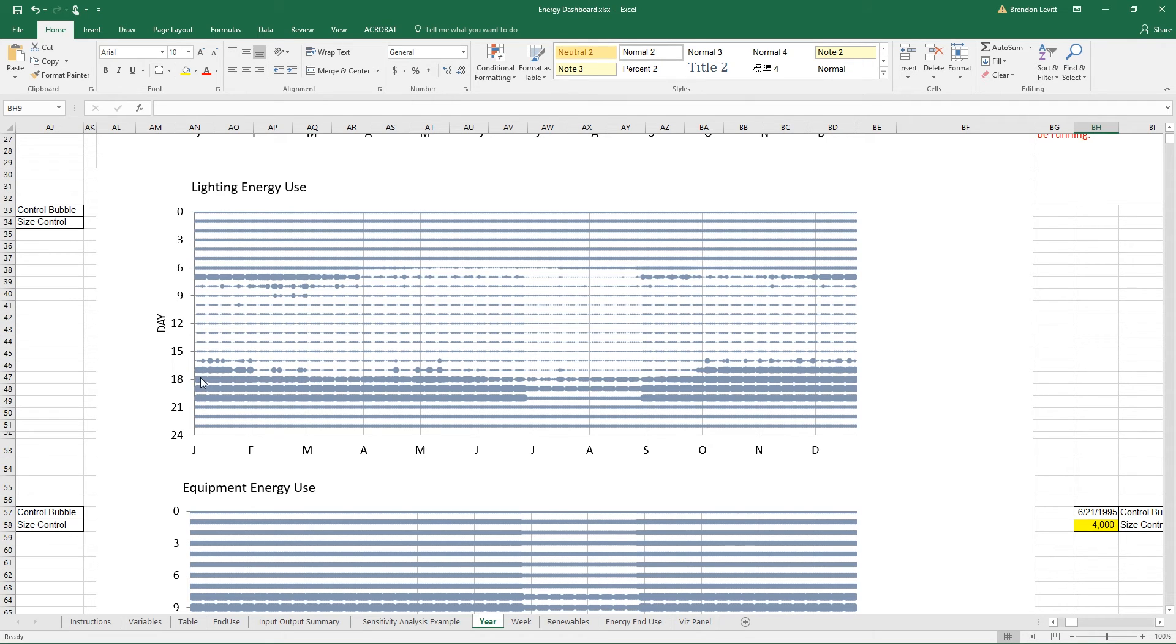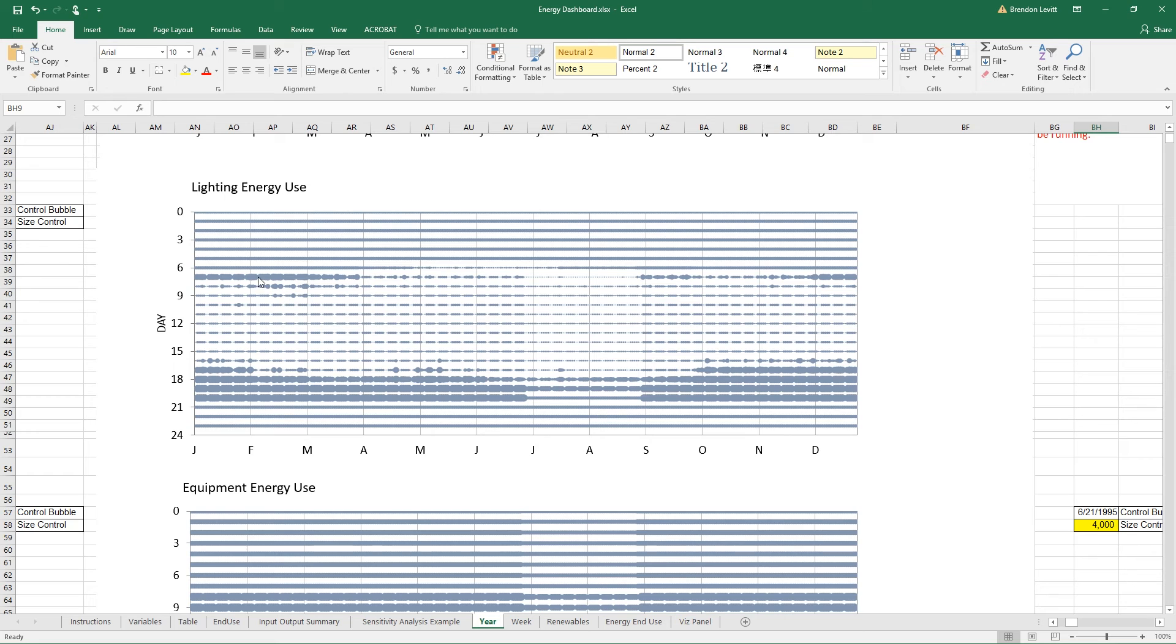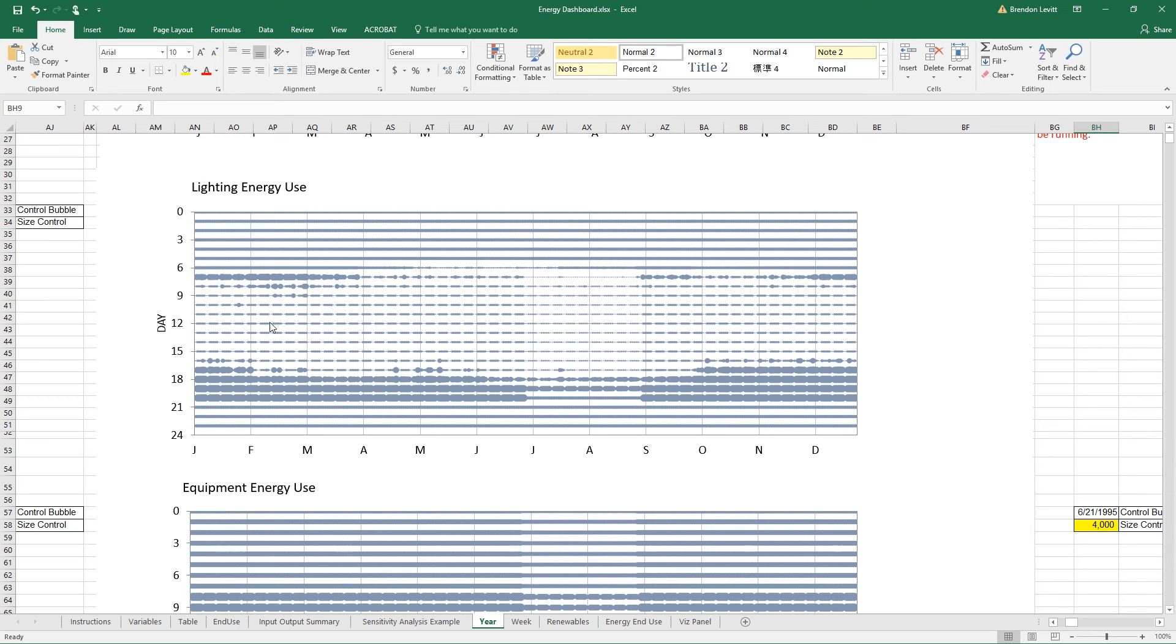And here at 5, 6, 7, 8 p.m., we're using a lot of electric lighting energy. By 9 p.m., the lights are off or in evening mode. So not on as much. You'll also notice that there are these assorted dots throughout that look like they might be cloudy days or cloudy mornings, at least, where we're getting less illuminance and so the lights have to be on more.